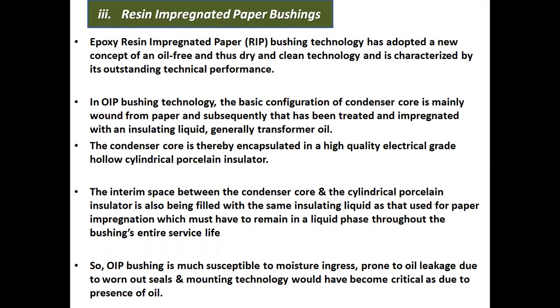In OIP bushing, oil impregnated paper bushing technology, the basic configuration of the condenser core is mainly wound from paper, which is subsequently treated and impregnated with an insulating liquid, generally transformer oil. The condenser core is thereby encapsulated in a high quality electrical grade hollow cylindrical porcelain insulator. The interim space between the condenser core and the cylindrical porcelain insulator is also filled with the same insulating liquid as that used for paper impregnation, which must remain in a liquid phase throughout the bushing's entire service life.